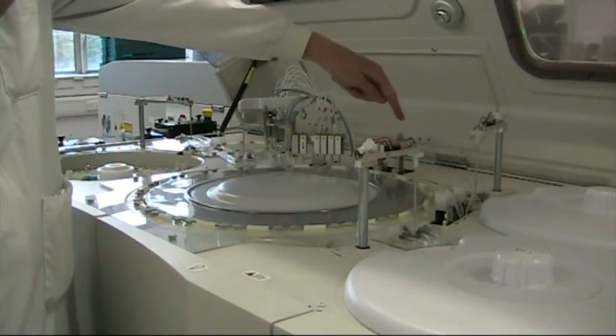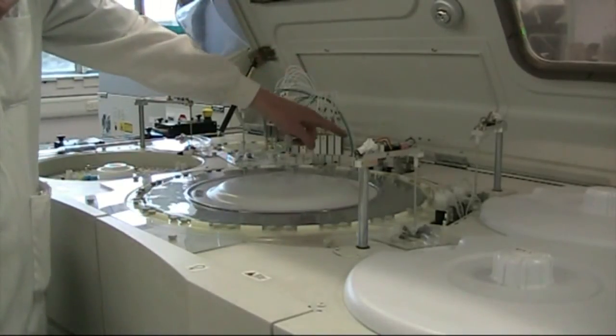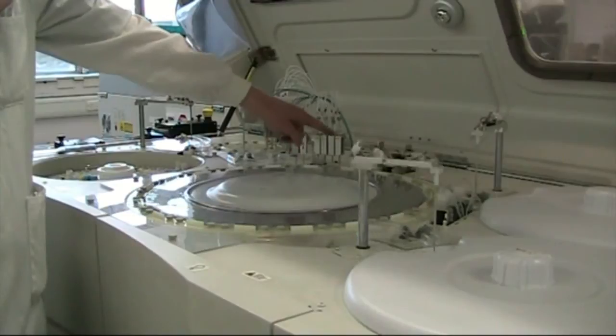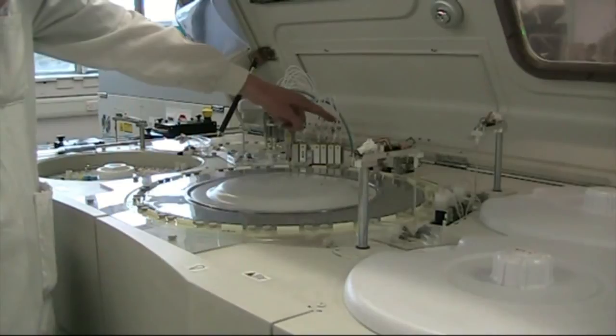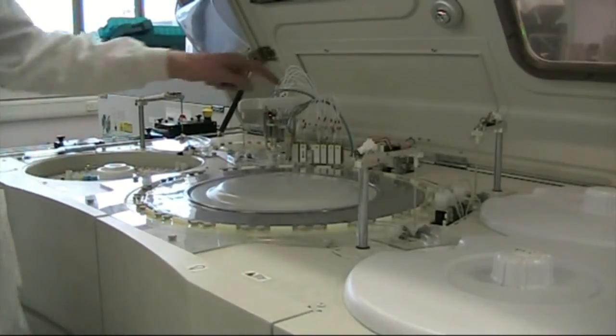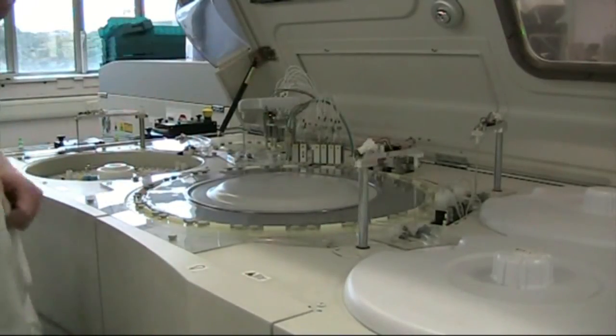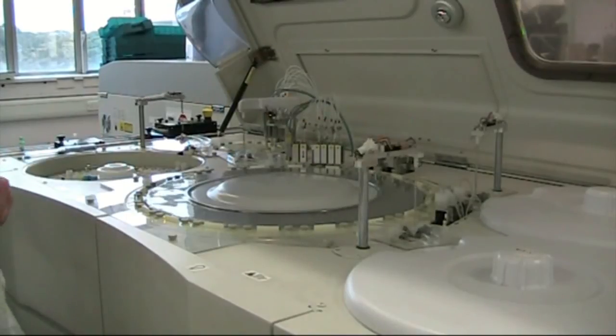And it then goes through mixing. So we've got a Mixer 1 and a Mixer 2 here, which come out and vibrate backwards and forwards and spin around very quickly in the cuvette. You can see that now. That ensures that the sample is mixed effectively.